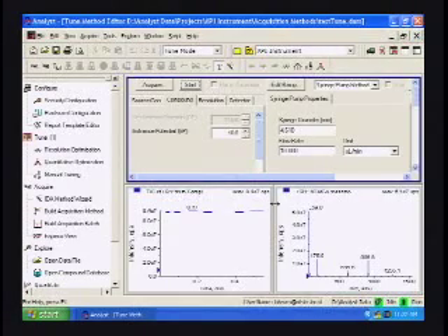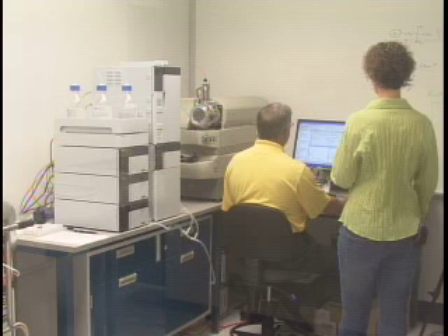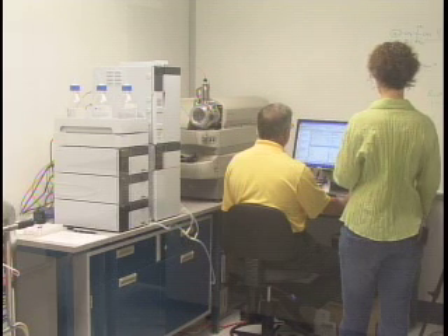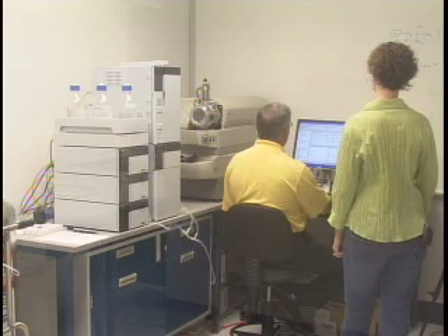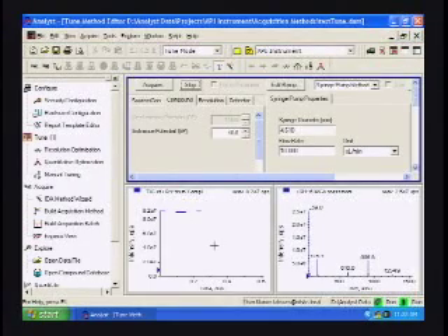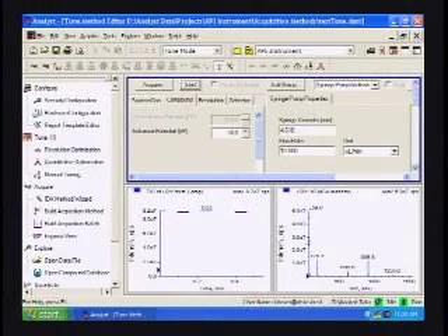Let's click on Start again. Now that total ion chromatogram pane is good to use, so you can tell that you have a nice, steady, stable signal throughout the time it's collecting the scans. If this signal were to drop down to 0 and come back up again, that would usually be indicative that there's an air bubble in the line. And because it's doing additive counts, that particular run I would never attempt to use. And again, this total ion chromatogram looks pretty stable across the 10 scans.